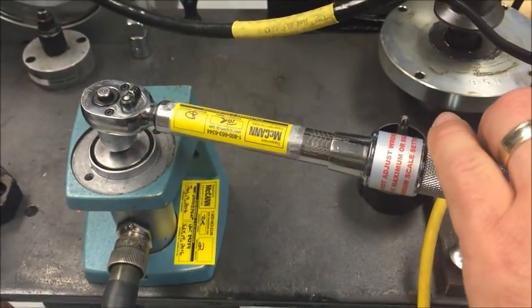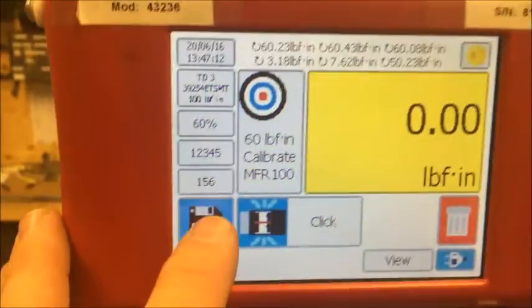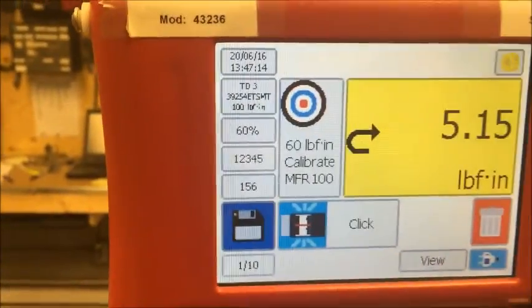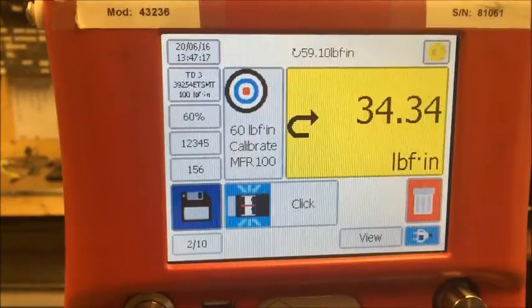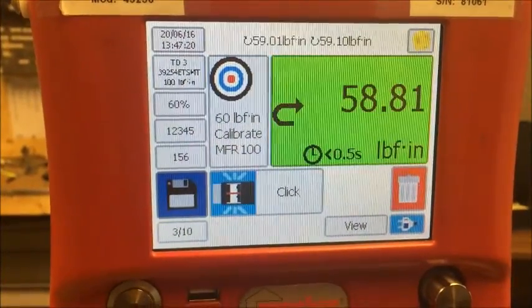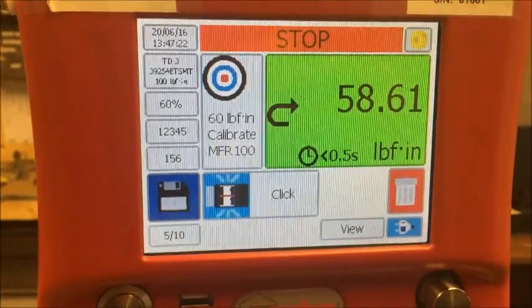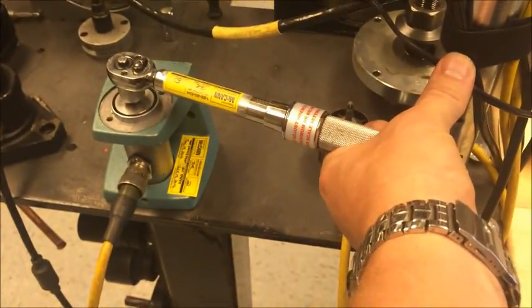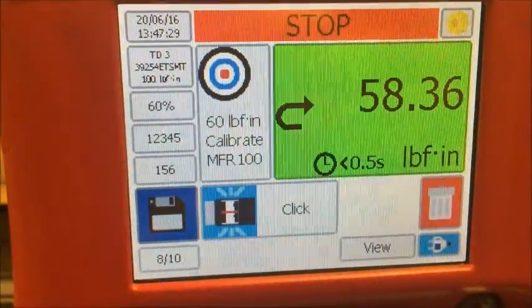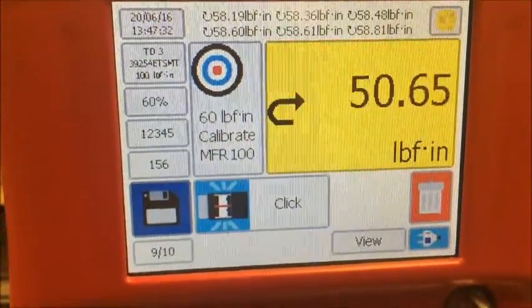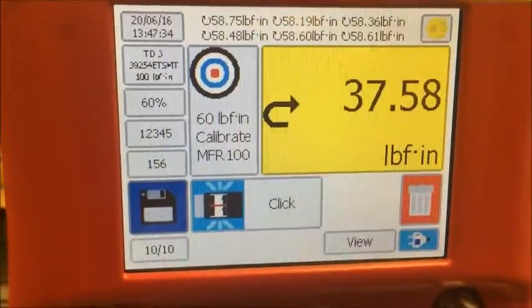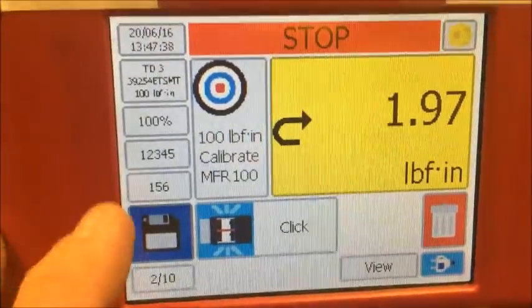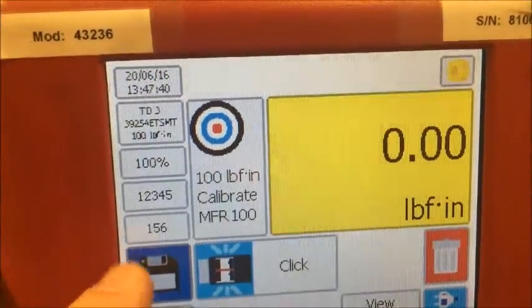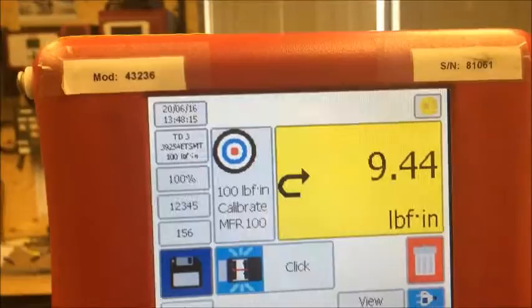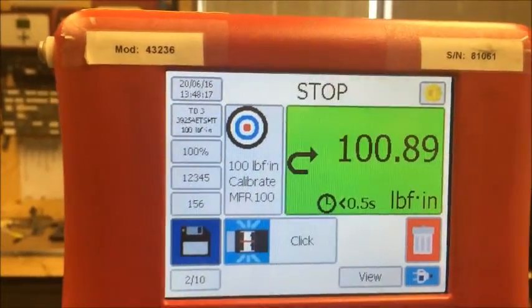So I've set the wrench to 60 inch-pounds. I can turn record back on, and we're getting our in-tolerance readings again. You see them counting up in the bottom left corner. Number 10. So now it's jumped up to 100 automatically. I'm going to turn off the record while I adjust the wrench again. So now I'm set to 100 inch-pounds.